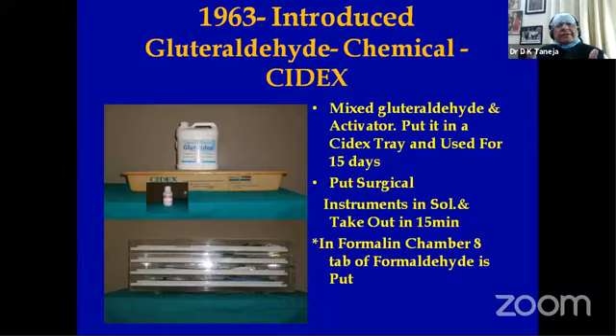Now we all have been seeing this glutaraldehyde chemical, which is an aldehyde group of chemical, and which is marketed by Cidex, by the Johnson & Johnson company. And this is mixed with an activator, and then it is put into a Cidex tray like this, and you can put your instruments into this for sterilization. But if you want your spores to be killed, then you have to leave it for a much longer time, and maybe it's good to leave it overnight before you can get a satisfactory result out of this.